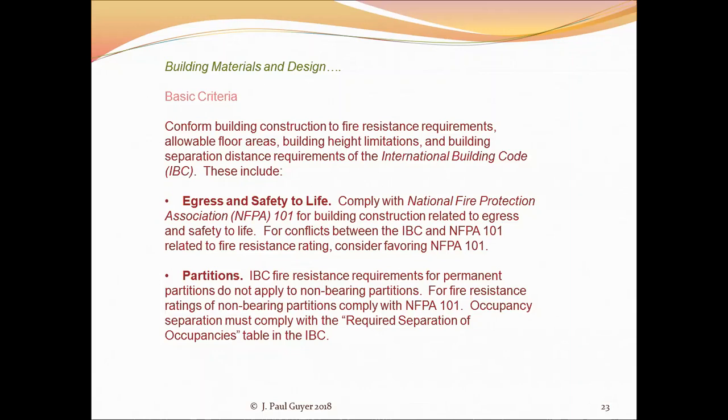The commercial interests in the building materials business, the gypboard people, the steel stud people, et cetera, they want to be able to market their products, their materials, and to be able to say to the engineers and architects that are designing these buildings, well, if you design the partition this way, 6-inch steel studs at 16 on center with 5/8 gypboard each side, that it will have a fire resistive construction of 1 hour or 2 hours or 3 hours.